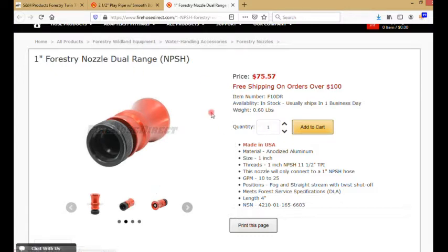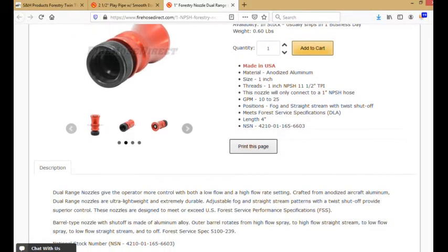And then you would look at how much flow you had coming out, and then you would time it to make sure that you're actually getting it, because on a combination nozzle you're only going to get the true flow of, let's say, 25 gallons a minute if it's on a straight stream, basically opened all the way up. So if you shut this down to like 10 gallons a minute, that's telling me that that's probably going to be closer to a wide angle fog. 25 is going to be a straight stream, 20 is probably going to be closer to a narrow fog or a medium fog, and then 15 is even narrower than that. That's what that's telling me in my mind. Now that may not necessarily be accurate, but that's how I would look at that.